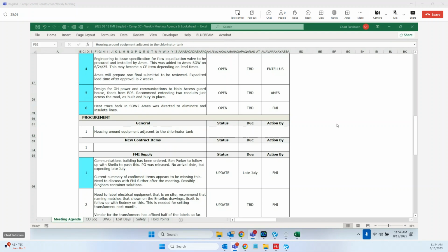At the end of the chlorine contact tank, the plans show a weir, just a rectangular weir. That was put there in case we needed to add some type of trimming of the chlorine. Sure enough, because of the variations in flow we're going to expect and what the analyzer would require, we're going to add an ultrasonic device. It'll simply be installed over the weir that's part of the plans, and that will send a signal back through the PLC mounted at the effluent pump station. It's just an I/O thing.